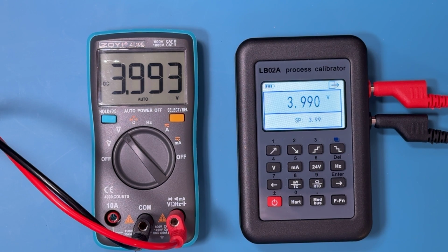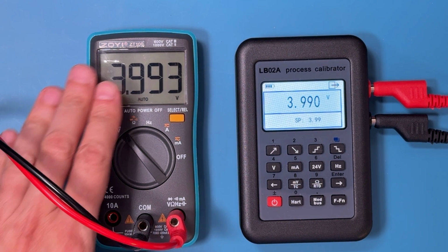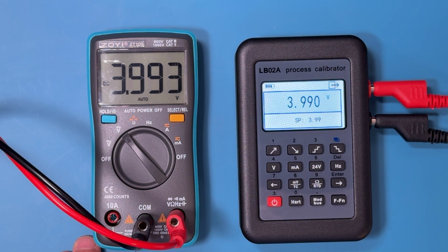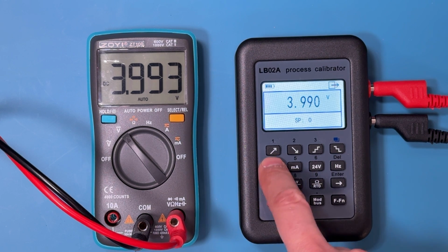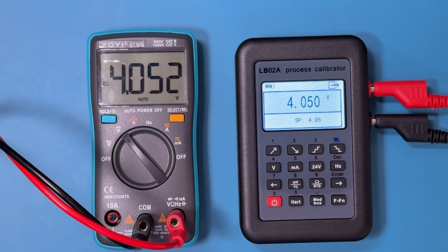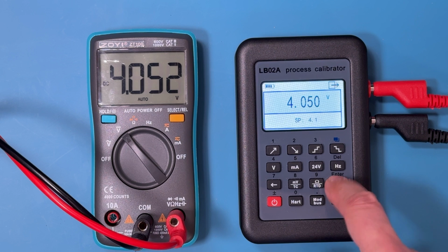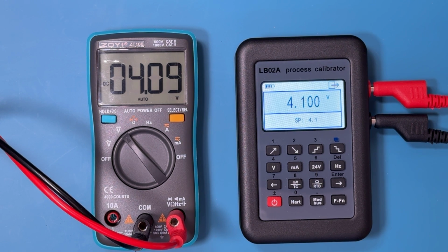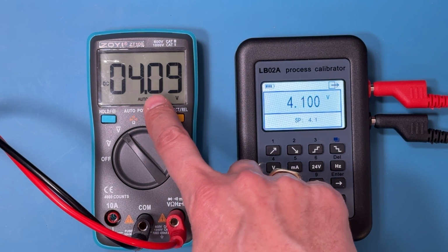Here's an example of a multimeter going slightly beyond its specified counts. This Zoyi ZT100 is a 4,000 count multimeter. The highest value it should show in the current range is 3.999. The calibrator is set to 3.99 volts, and we are seeing 3.993 on the meter. When I change the calibrator over to 4.05 volts, I should lose a digit, but I don't, and you can see the reading at 4.052. Now, if I push the voltage up to 4.1 volts, the meter finally goes into the next range and a digit is removed, and so I only see 4.09.